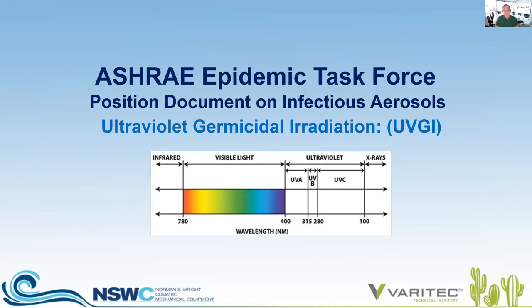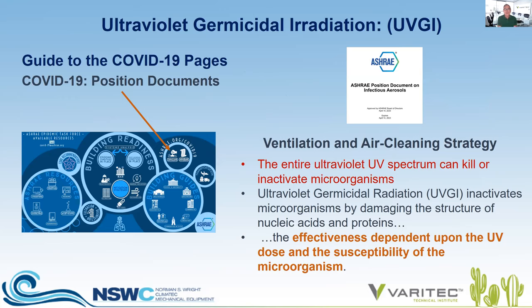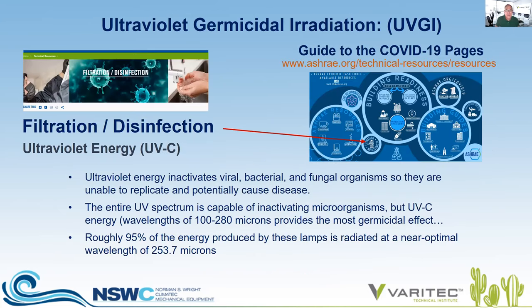Before we move further, let's validate why UVGI is being given every consideration. ASHRAE's Epidemic Task Force position document on infectious aerosols, under the ventilation and air cleaning strategy section, states that the entire ultraviolet UV spectrum can kill or inactivate microorganisms. Ultraviolet germicidal radiation inactivates microorganisms by damaging the structure of nucleic acids and proteins, with effectiveness dependent upon the UV dose and the susceptibility of the microorganism.